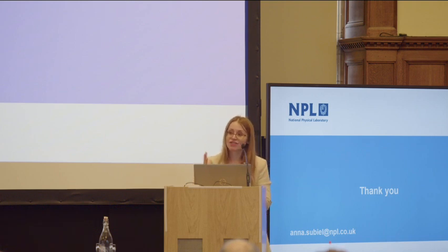But we can have another talk just on 2D dosimeters, and they will be incredibly important because, let's face it, very often, especially the research beams that are being currently used for flash radiotherapy, they are not beautiful homogeneous beams. They very often have some sort of Gaussian distribution, God forbid, some heterogeneities, which are even more complicating the situation. So yes, 2D monitoring is very, very important.